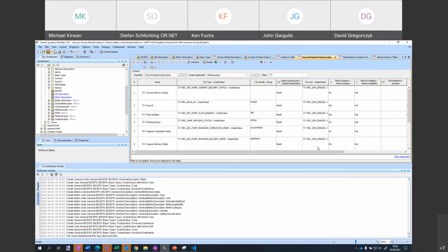you know, part of the SDPi supplement is volume 3, which has device specializations, which will have an infusion pump, a BICEPS infusion pump. And the content that we'll put in the supplement, which is a document, because that's the way that works right now, will be generated or captured out of this model. So at least, and then it'll have pointers into the device specialization infusion pump model.